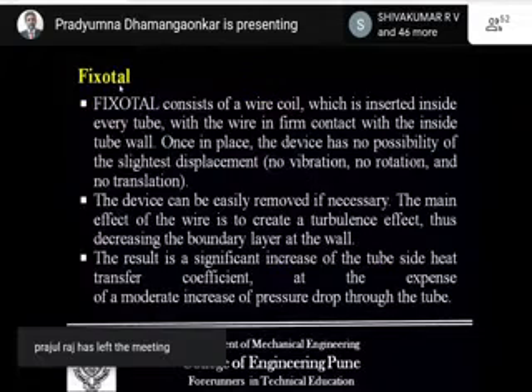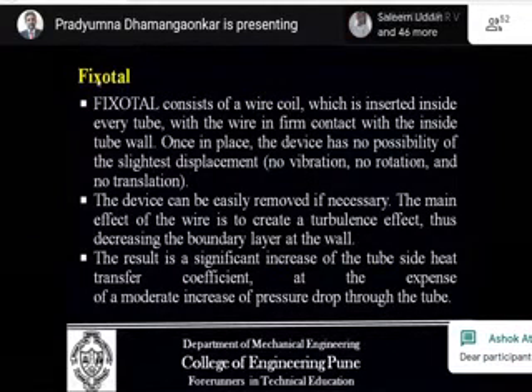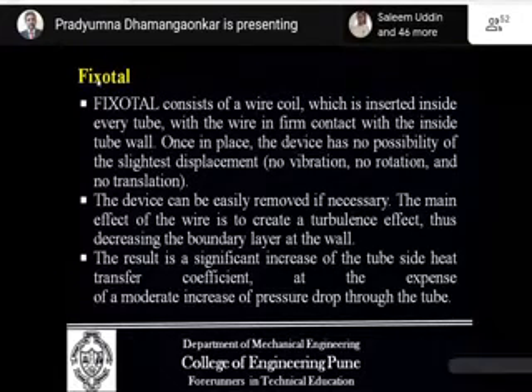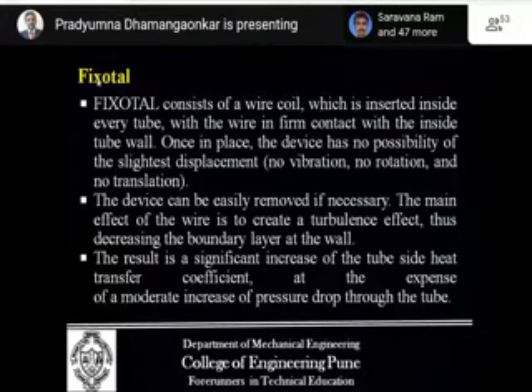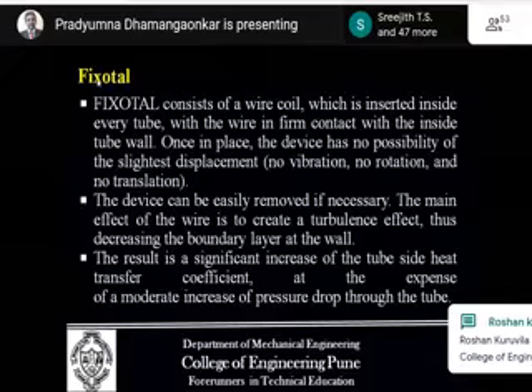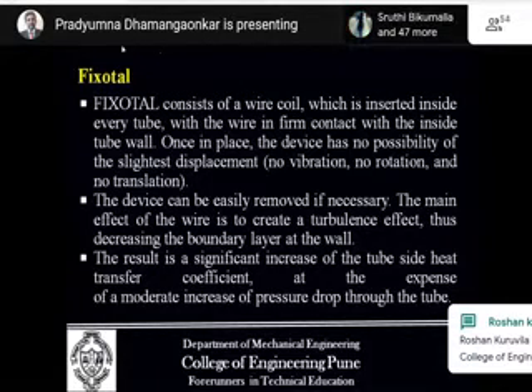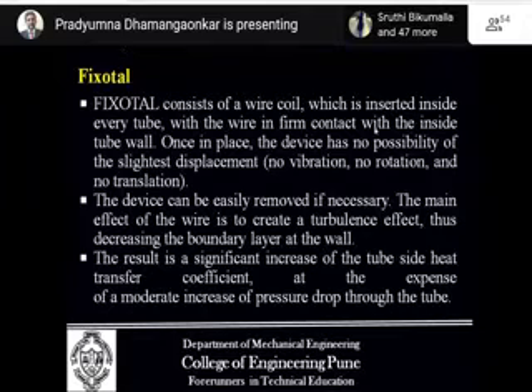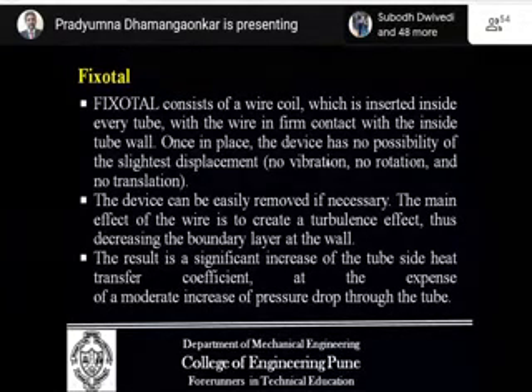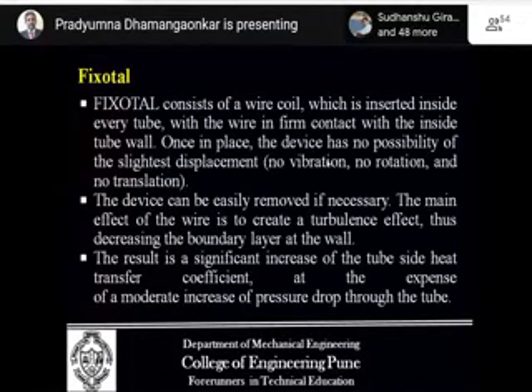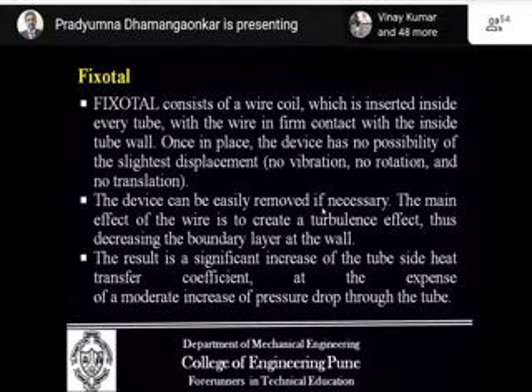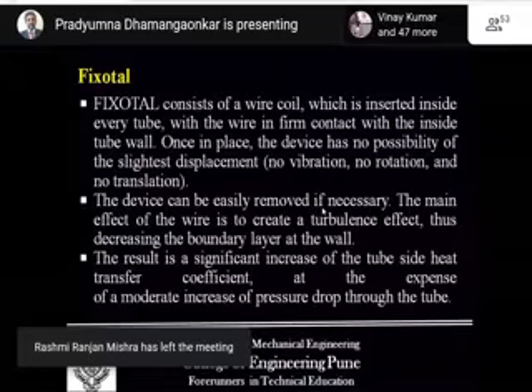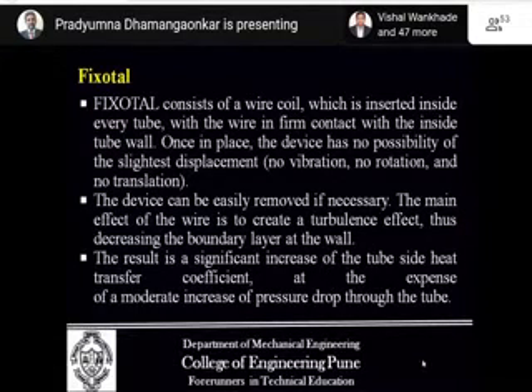Fixotal goes along with its name. It is also a sort of wire coil, a spiral coil, but the only difference is that during the entire operation, this wire is fixed at both ends and fixed with the surface. Always the wire is fixed with the surface. It is a wire coil which is inserted inside every tube. Once it is fixed, it has no possibility of displacement, hence no vibration, no rotation, no translation, and thus the device can be removed easily for whatever maintenance is required, and it has a very high performance rate and very low pressure drop.